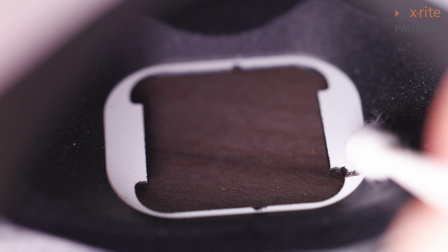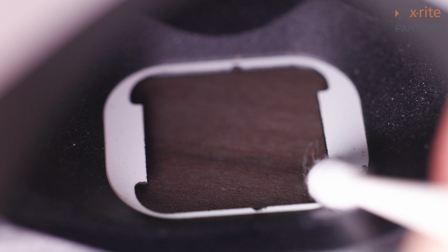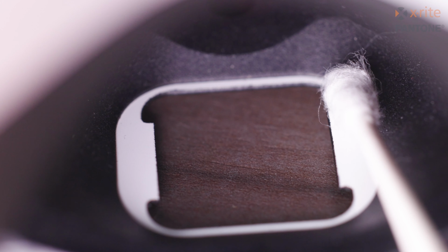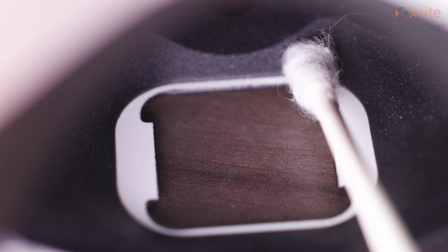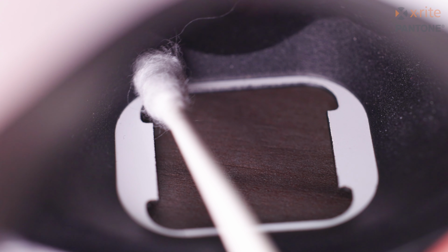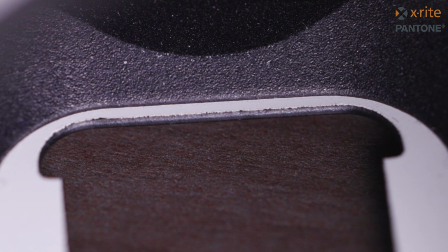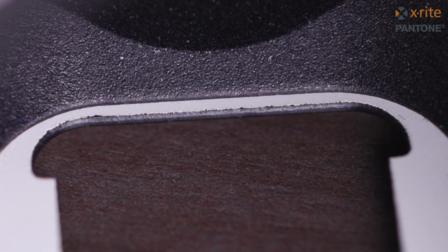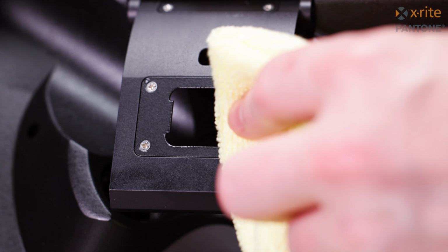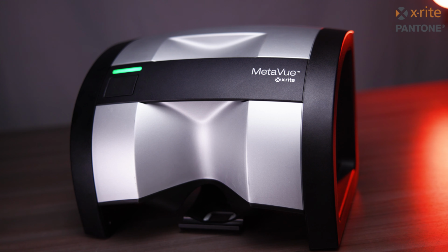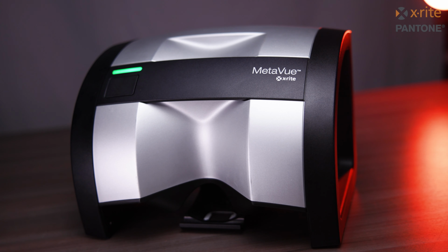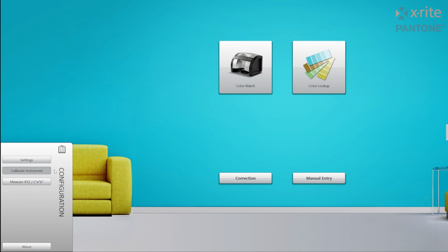Clean the white tabs on the left and right side of the target window with alcohol. Also ensure the small white lip around the outer edge of the target window is clean. Use a Q-tip and alcohol if needed. Make sure to inspect the sides of the tabs for contamination or paint buildup, along with the bottom of the target window. After you have completed the cleaning process, attempt to calibrate the unit again.